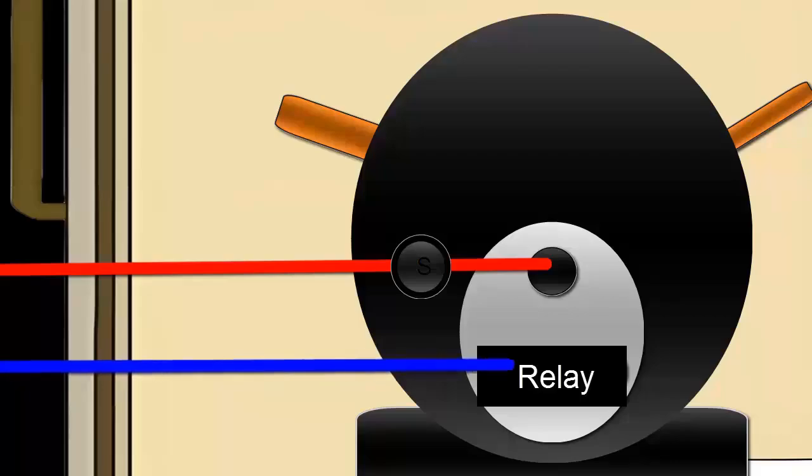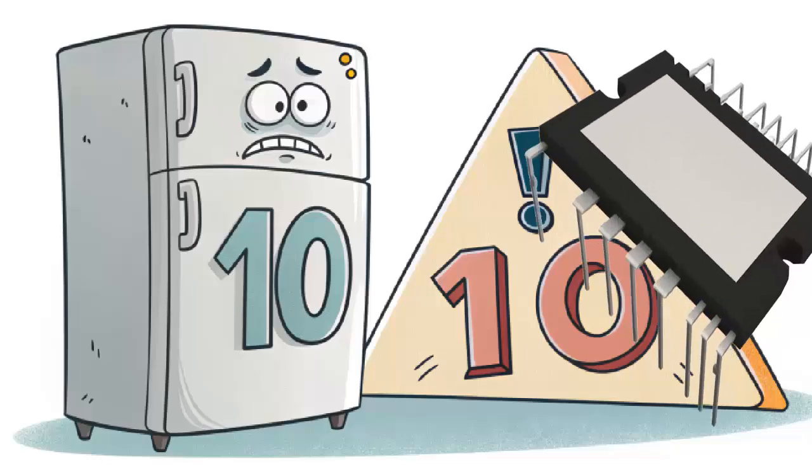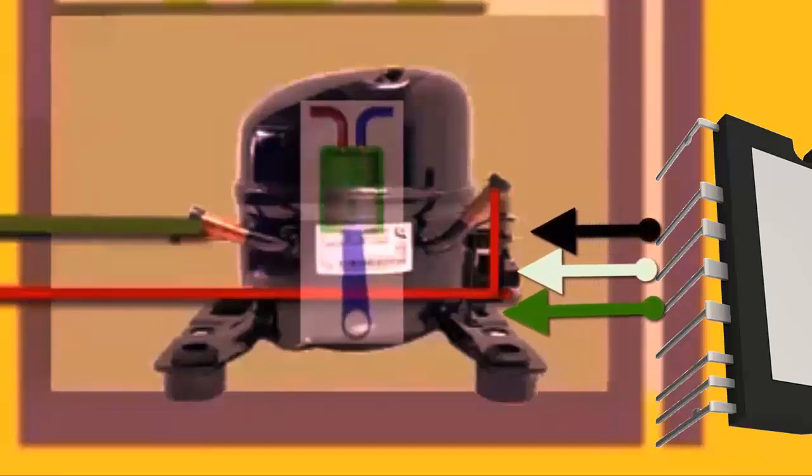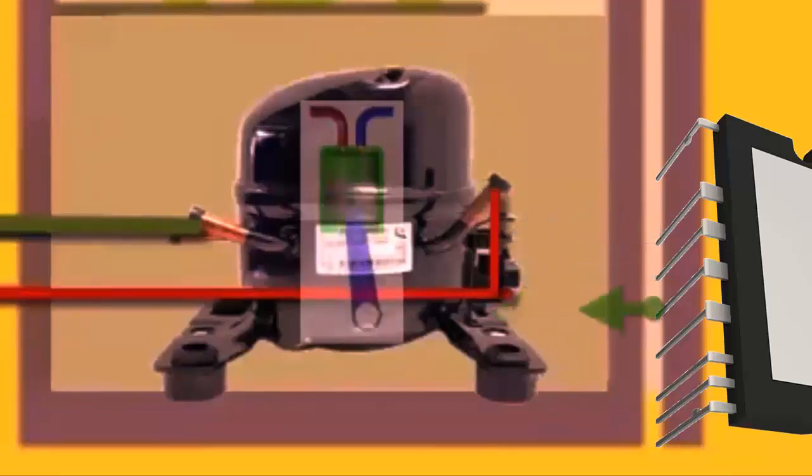10. In inverter compressors, a failure in the intelligent power module located in the electronic control board can lead to excessive current draw. This forces the electronic control system to shut off the compressor quickly for safety.